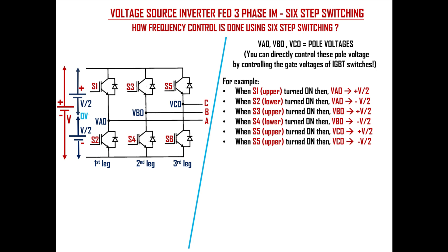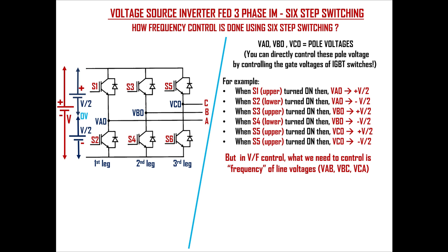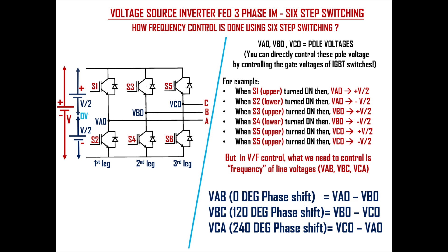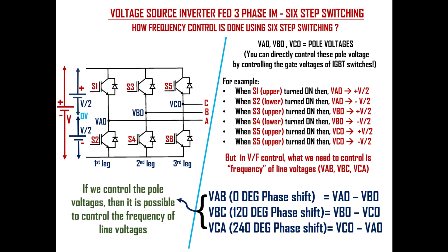Similarly for the second leg and third leg transistors. But what we need to control is the frequency of line voltages VaB, Vbc, and Vca. We can write VaB as Va0 minus Vb0, Vbc as Vb0 minus Vc0, and Vca as Vc0 minus Va0. We need to keep in mind that the three line voltages should have 120-degree phase shift. So if we control the pole voltages by controlling the gate voltages of IGBT switches, then it is possible to control the frequency of line voltages.